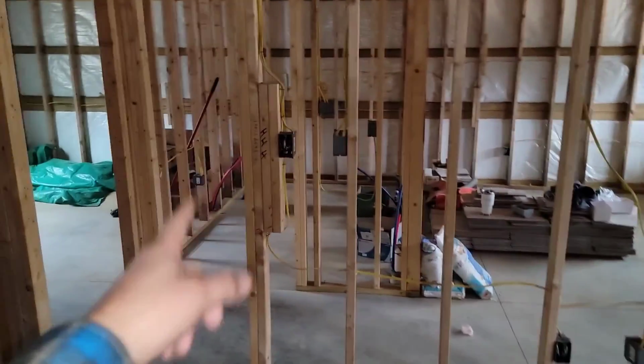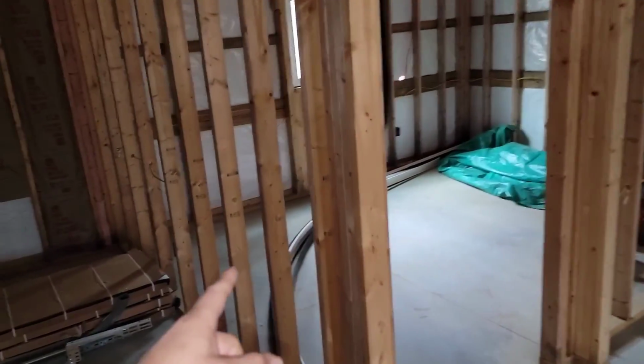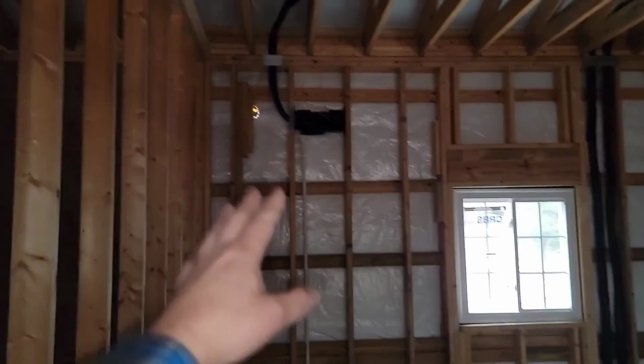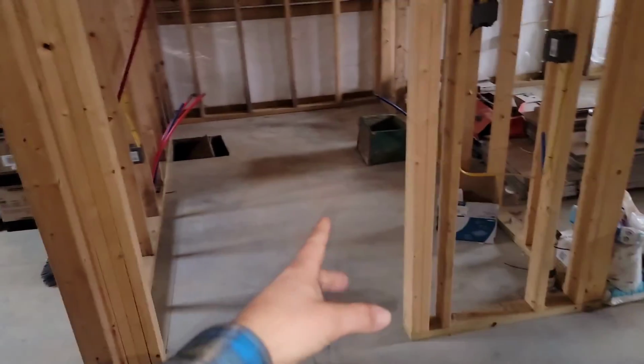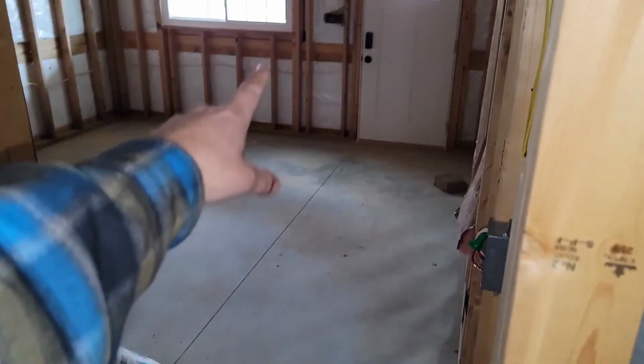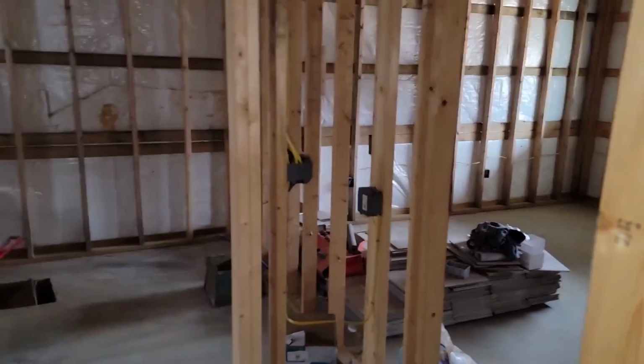Now we got a bedroom, a bathroom, and another bedroom. And instead of adding a mini split wall mount air handler in here and in here, I just got one right there on that wall. And that air will travel through this door, hit the bathroom, and we got a bath fan, of course, that'll pull in air, and it'll go into this room. So was able to save some money on the total price of the job.